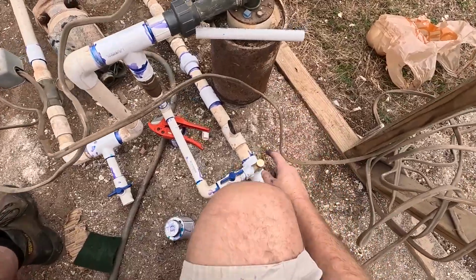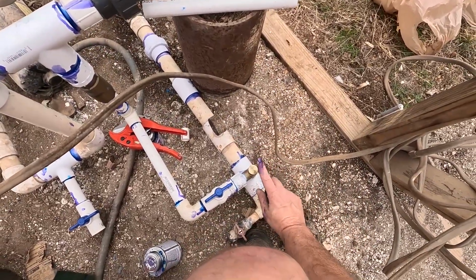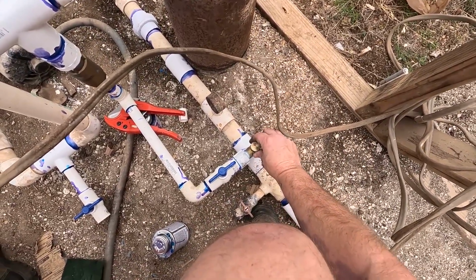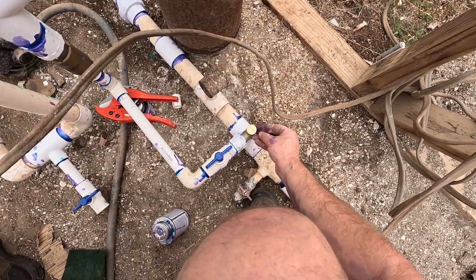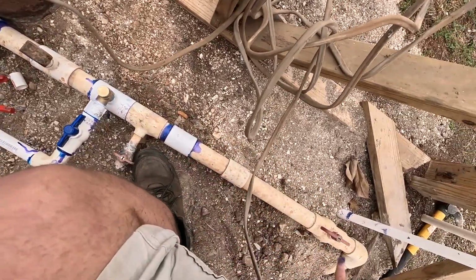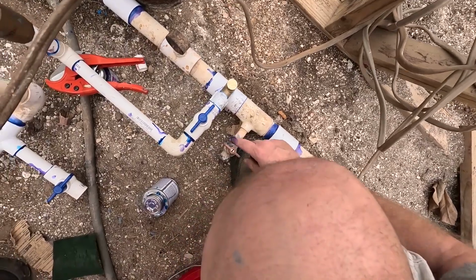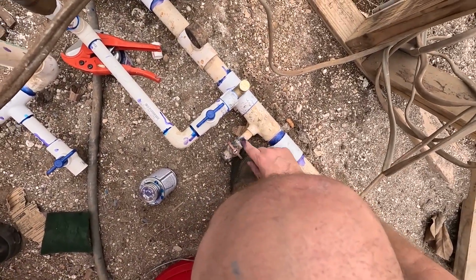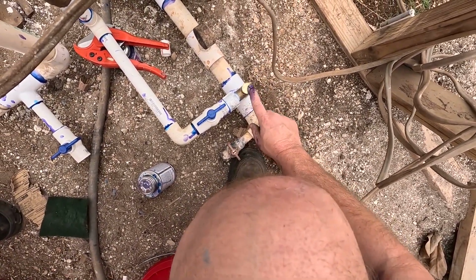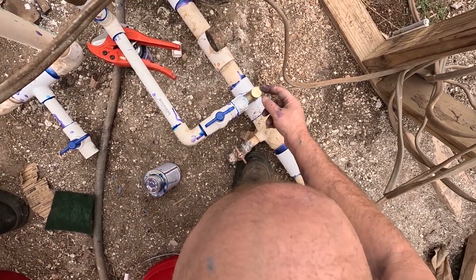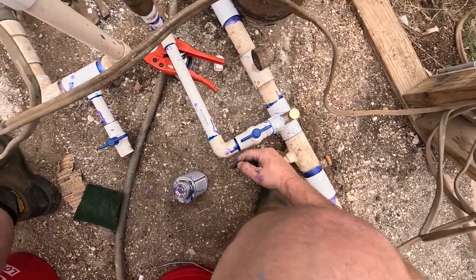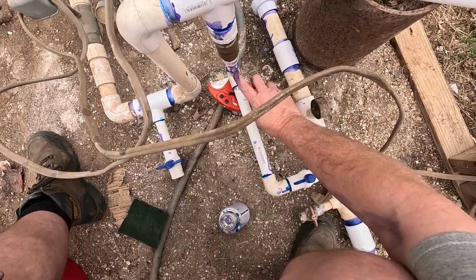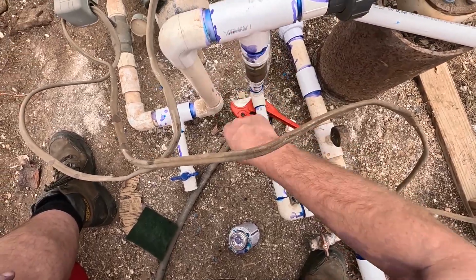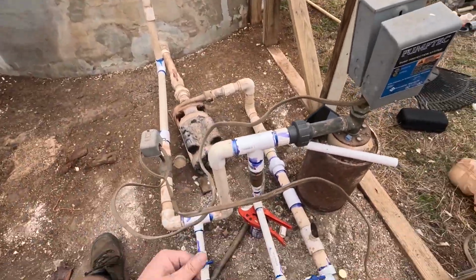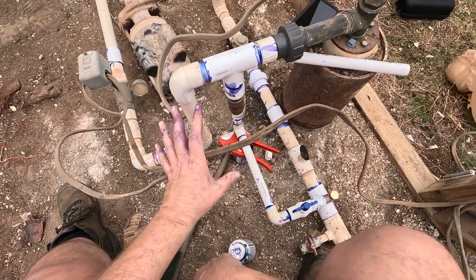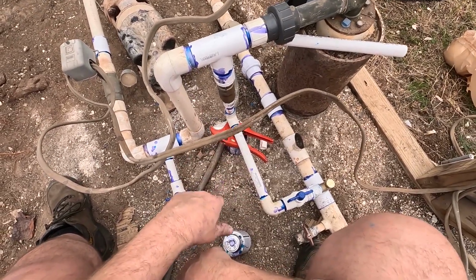Comes through there, pressure gauge, overflow valve, and this is set to 75 psi, and it keeps going out to the sprinkler system, right? And this is a low point drain. And then any pressure over 75 psi will bleed off into here, up, it'll push this valve open into here, and pump it back into the tank. So as far as the pump and the irrigation system, we're finished.